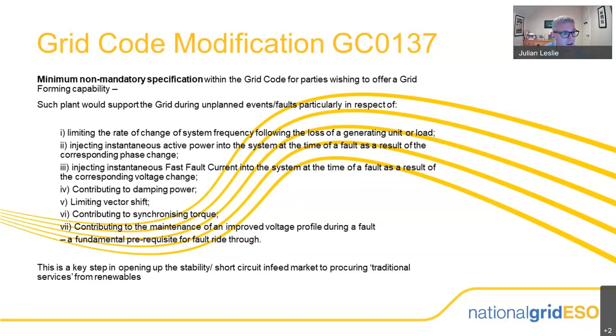From our perspective, what it allows the market to do now is that when they're building an inverter-based product, they can look at the requirements and our future inertia requirements on the network. They can look at the size of the markets I've just spoken about and say, actually, for a relatively small additional cost now, I can put in this grid forming inverter, and that means I can participate in those markets into the future. This way, as a system operator, we will have a mix of renewable generation with grid forming inverters, combined with some of the devices and technology I've just been talking about, which is still physically rotating. I think that mix of technologies across the system is going to give us the confidence and resilience that we need in order to operate a zero carbon grid.